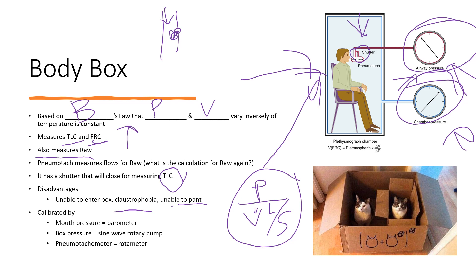To calibrate the body box, you need a barometer to calibrate mouth pressure, a sine wave rotary pump for box pressure, and a rotameter for the pneumotachometer. These three devices together ensure the body box is properly calibrated before use.